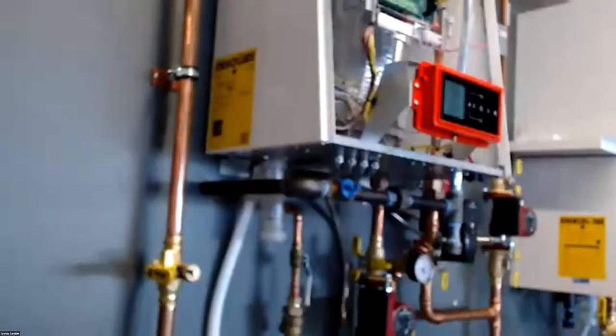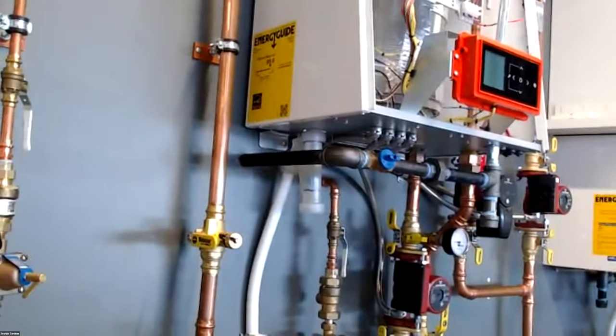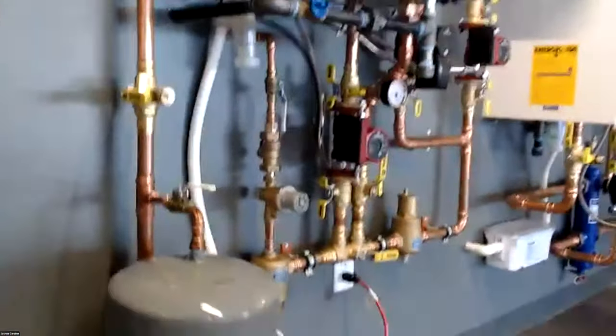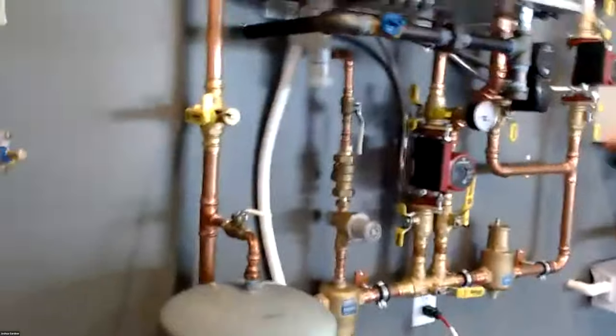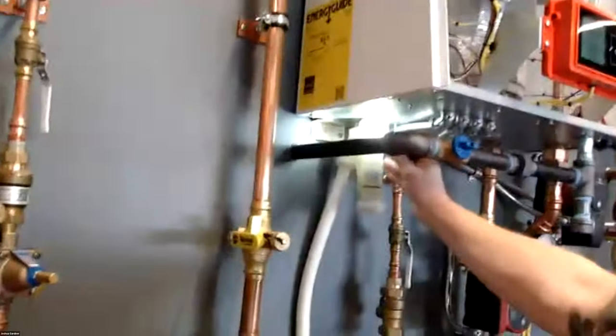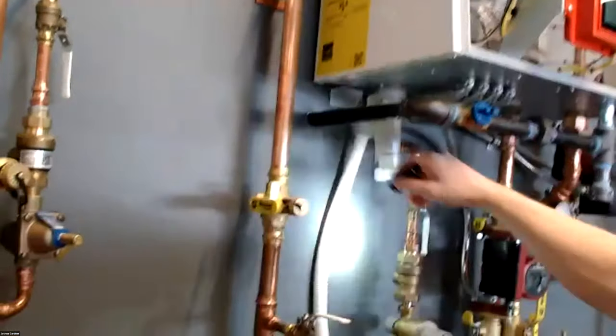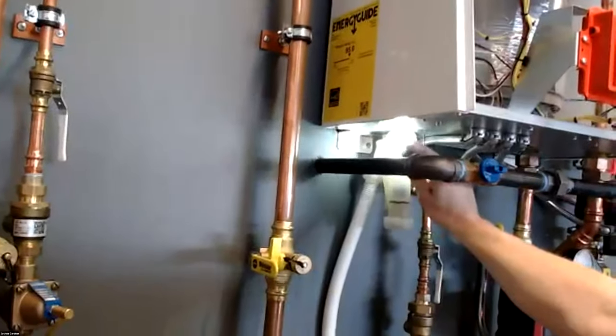The other thing I want to hit on the condensate trap is located inside the unit, but on our heat only boilers currently, our condensate trap is outside the unit, as you can see right here. Bear with me. I got cameras everywhere and boilers and wires. So one thing to note is that the condensate drip pan, so this is right up against the pan here, within like an inch or two. The nipple for the condensate pan protrudes outside of the jacket.